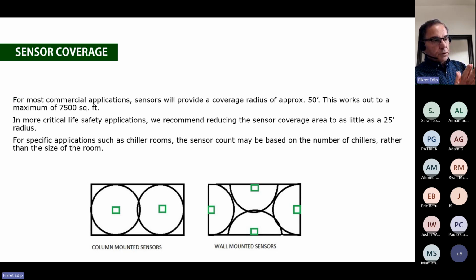In these images here, I'm showing you a perfect example of where you mount your sensor to have perfect coverage. In the image on the left, with two sensors mounted right in the center of the room, I can cover the entire area, or almost. But if you are limited to mounting the sensors on the walls of the premises, now you need more to cover. This often happens in car repair shops, where in the middle they put all the lifts where they lift the car up and down. There is no column in between, inside or in the center of the room. So we are forced to put the sensors on the walls of the premises, and that dictates how many sensors you need to put. So here again, the 50 feet radius does not apply, because I cannot cover everything.